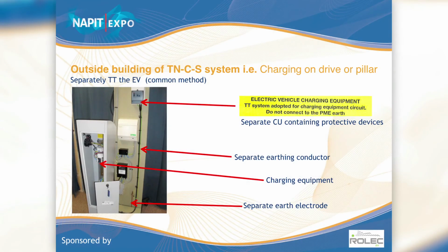That's a picture of the rig we've got next to us, although I've turned it round. It shows that, again, we'll go through it more on the course, but you can basically get rid of one earthing system, and that's a TNS system. Cable sheath you ignore completely, because with a cable sheath system you've got to get written permission from the DNO that they will never ever ever turn it into a TNCS system. They're not going to give you that. So TNS you classify as TNCS in the future. So you've only got two earthing systems to worry about, TT, TNCS.